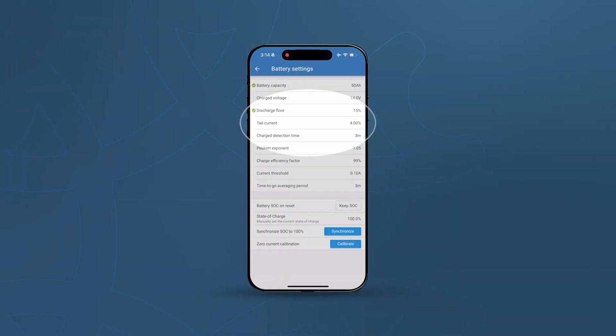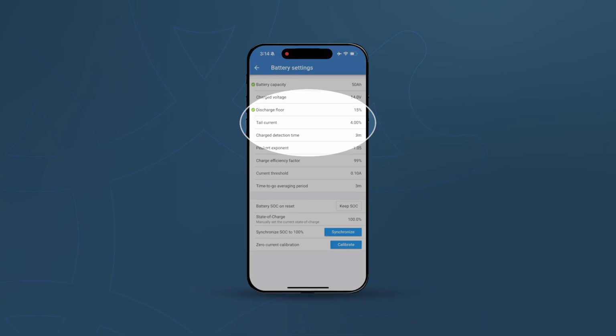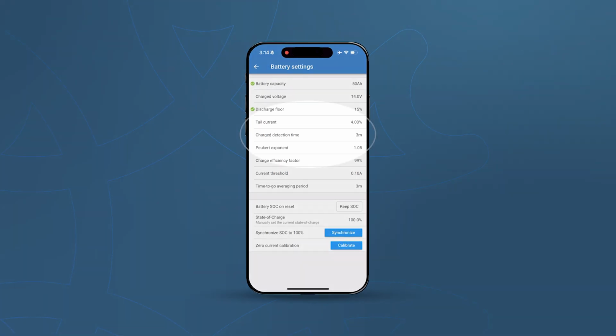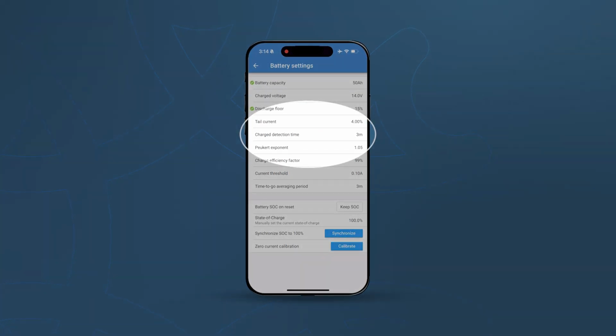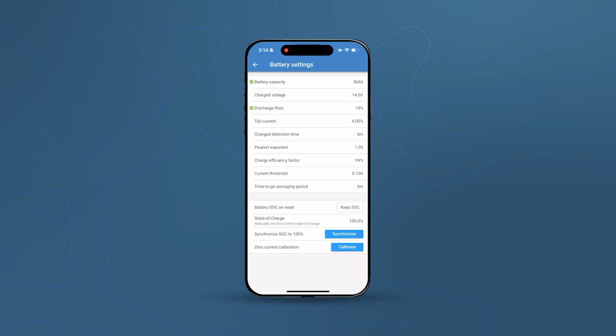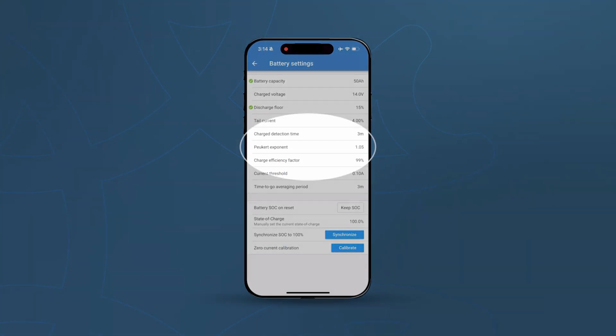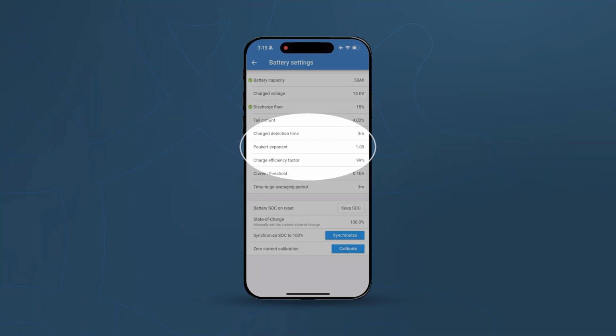The fourth parameter is tail current. I'm going to leave this as 4%. The charge detection time, I'm also going to leave at 3 minutes. And the Peukert exponent, I'm going to set to 1.05. This typically comes from the factory as 1.25.